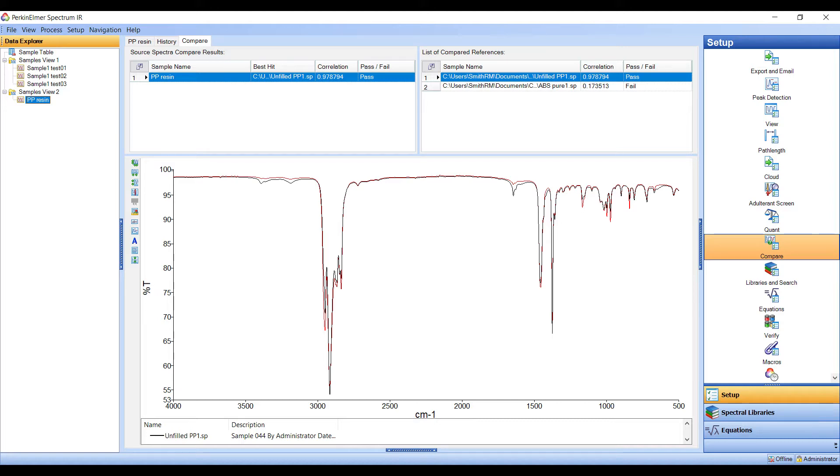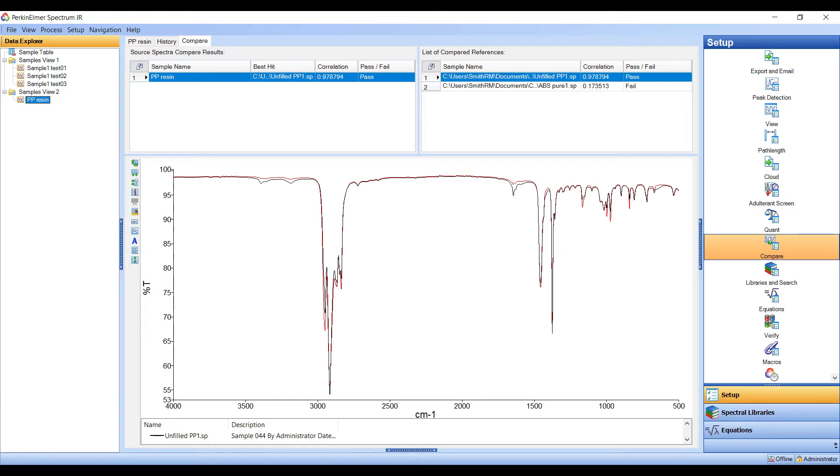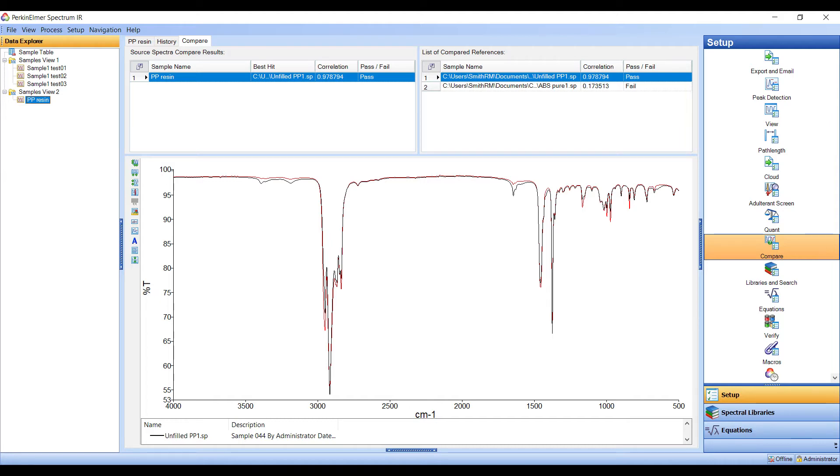It's generally accepted that a higher correlation value represents a closer match, a higher degree of similarity. And so the highest match is often taken as the true identity of the material, so long as it falls above a predefined threshold. This threshold is adjustable by users in the software.